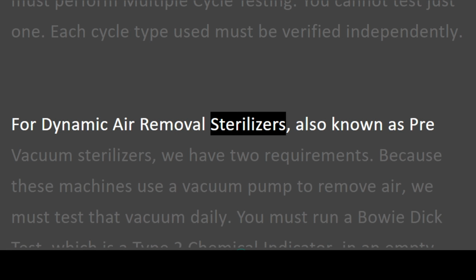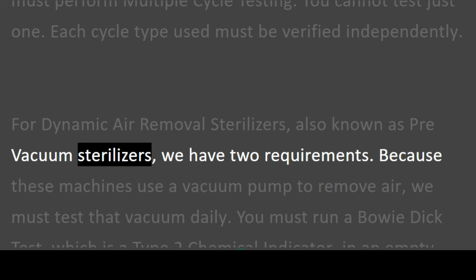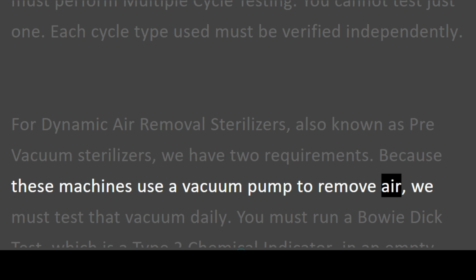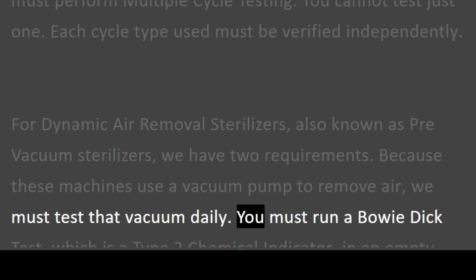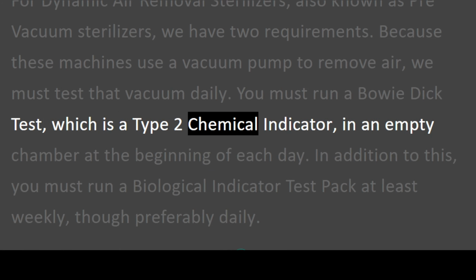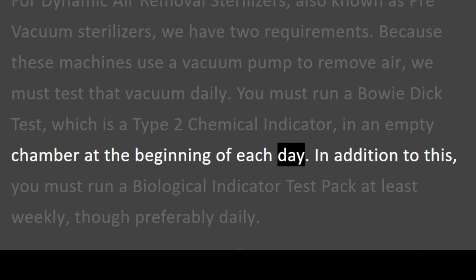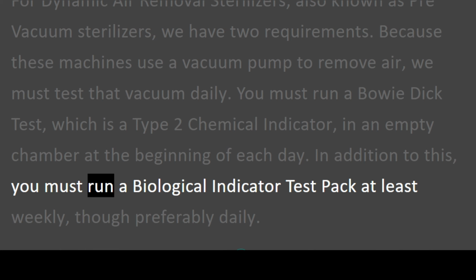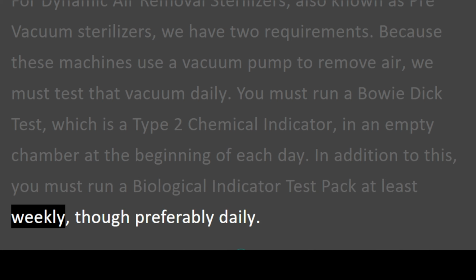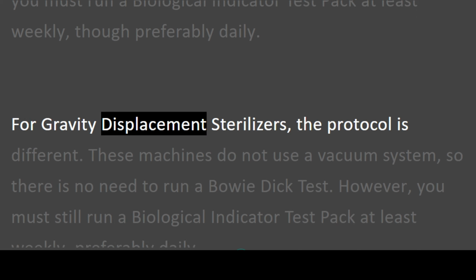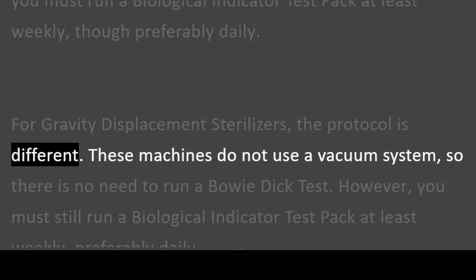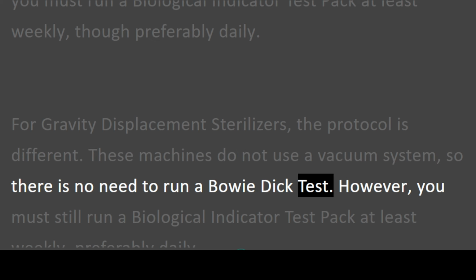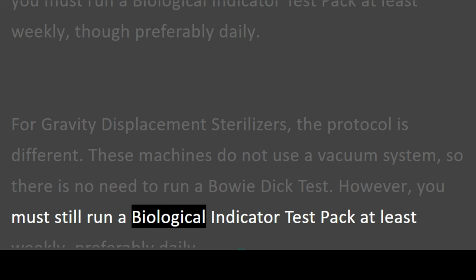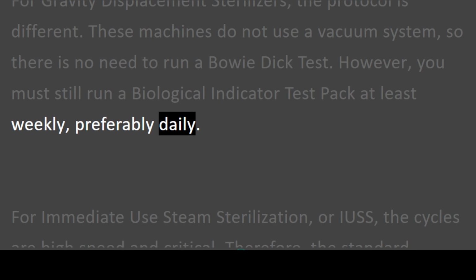For dynamic air removal sterilizers, also known as pre-vacuum sterilizers, we have two requirements. Because these machines use a vacuum pump to remove air, we must test that vacuum daily. You must run a Bowie-Dick test, which is a type 2 chemical indicator, in an empty chamber at the beginning of each day. In addition to this, you must run a biological indicator test pack at least weekly, though preferably daily. For gravity displacement sterilizers, the protocol is different. These machines do not use a vacuum system, so there is no need to run a Bowie-Dick test. However, you must still run a biological indicator test pack at least weekly, preferably daily.